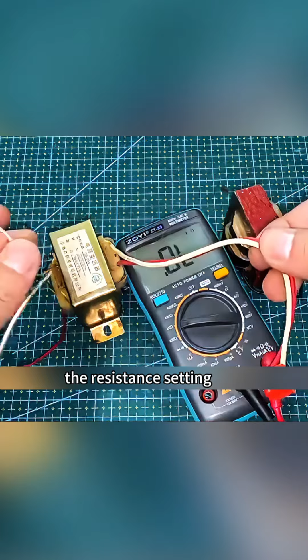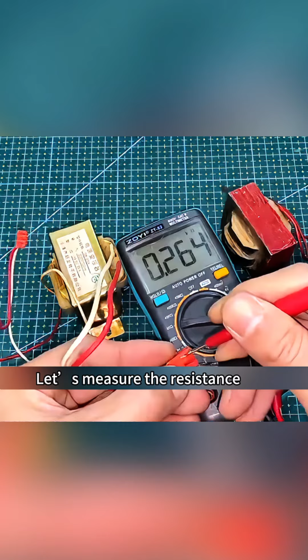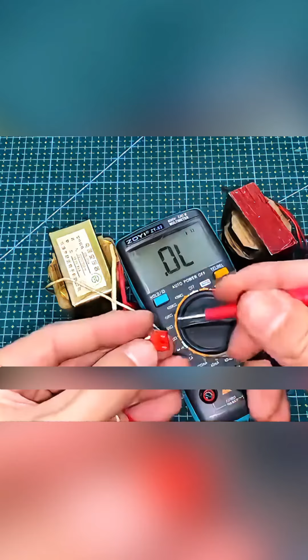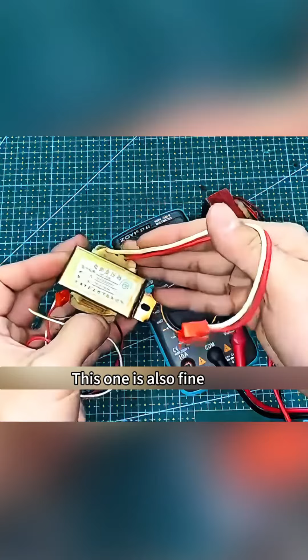First, set the meter to the ohm range, the resistance setting. This transformer has a few wires. These two are one group, and on this transformer the red wires are one group, black wires another. Let's measure the resistance on this side: 264 ohms, this shows it's fine, the coil hasn't burned out. Now let's measure the other side: 1 ohm, this one is also fine.